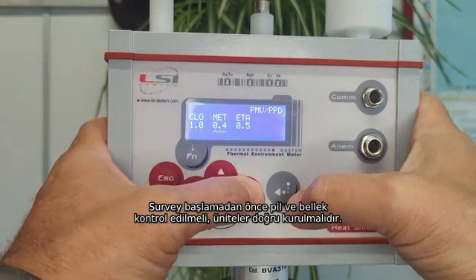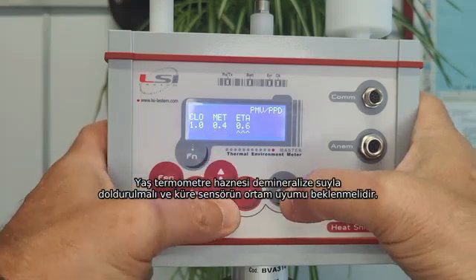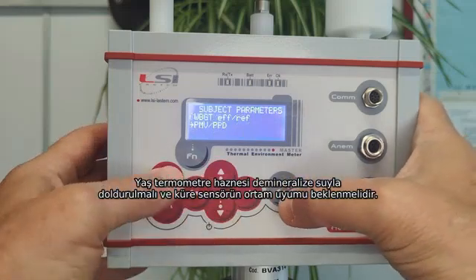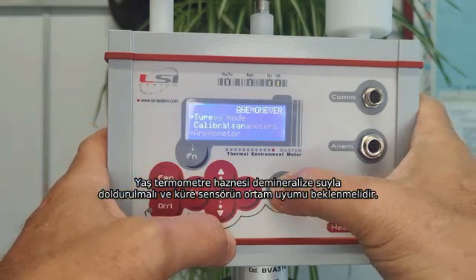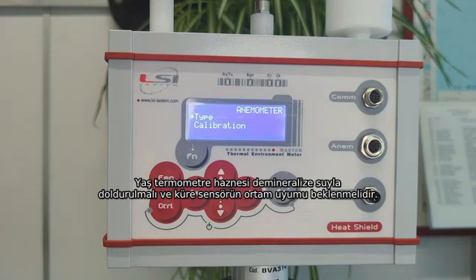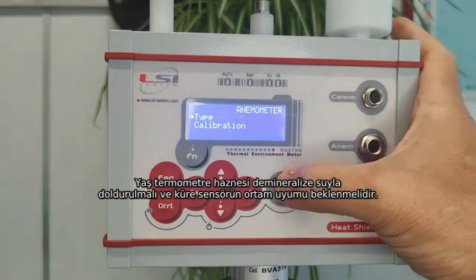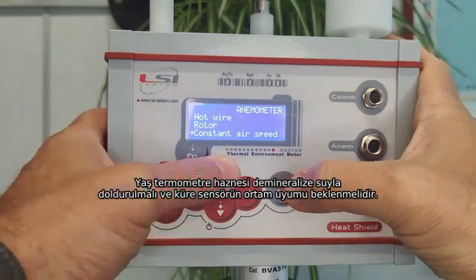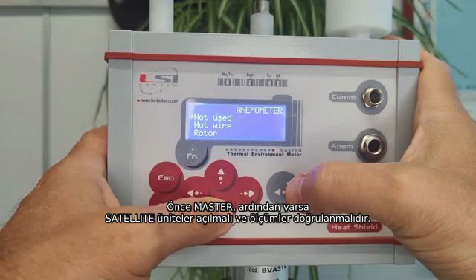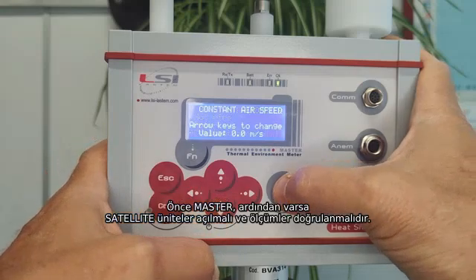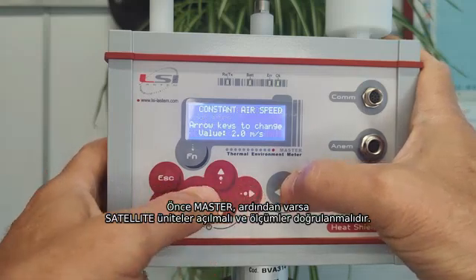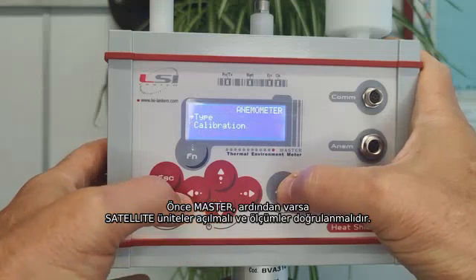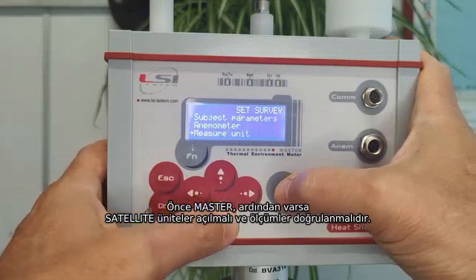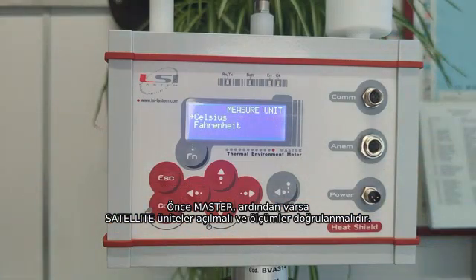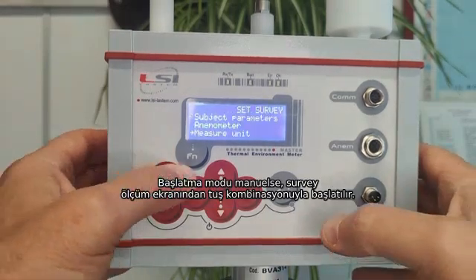For PMV-PPD calculation and whenever the small 5 cm diameter globe temperature is used, it is required to set the airspeed sensor type: not used, hot wire anemometer type, cup anemometer type, or a constant value, if any real anemometer is available. Then, we can decide the measurement unit to be displayed in degrees Celsius, or degrees Fahrenheit. When this has all been set, we can go back to the measurement list.